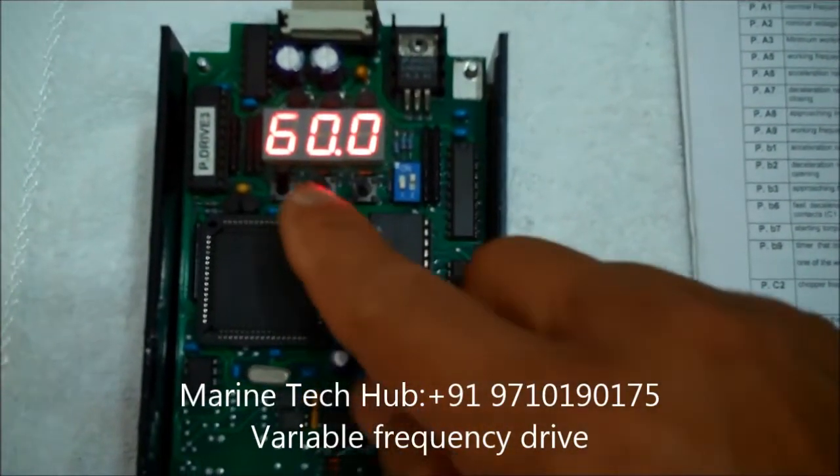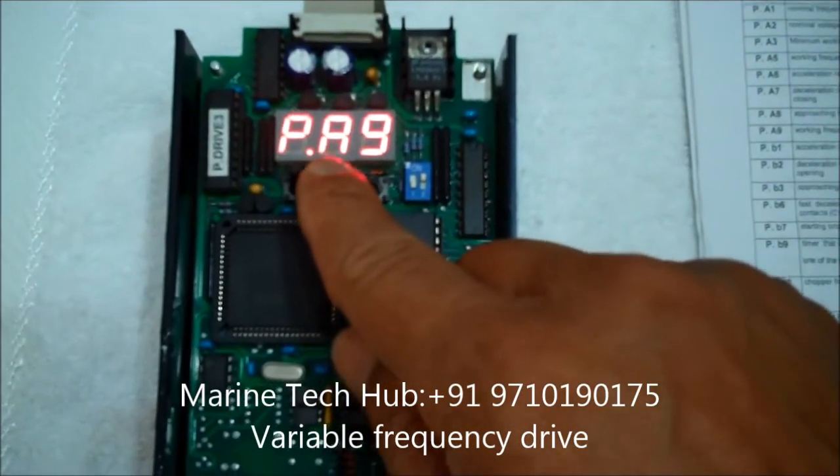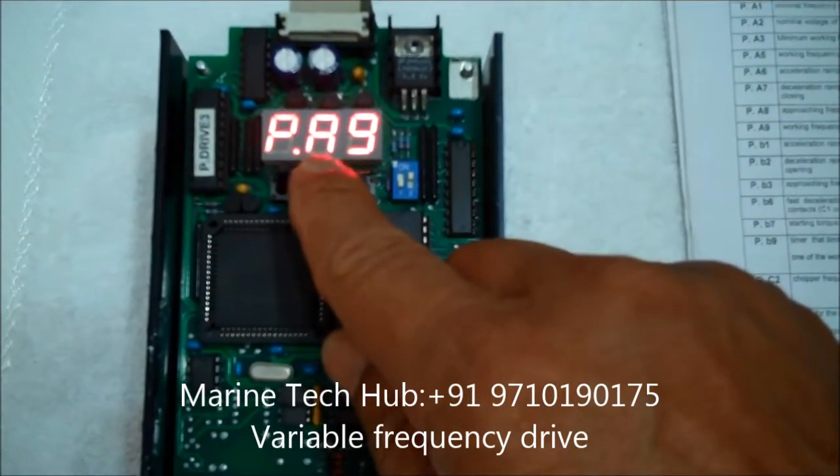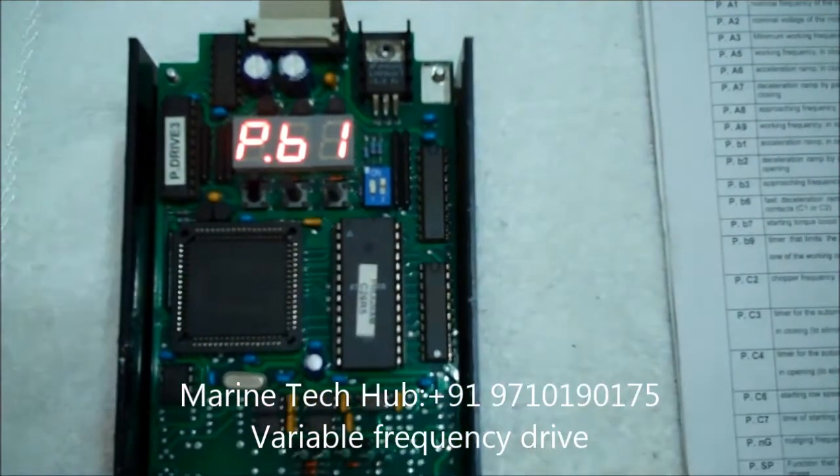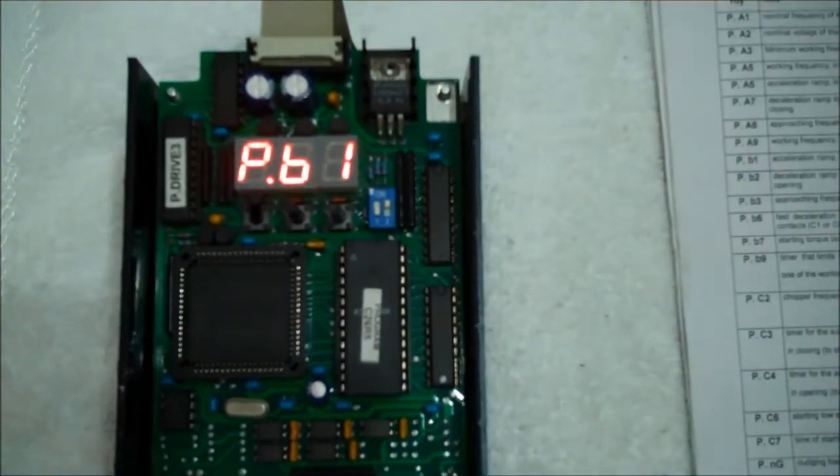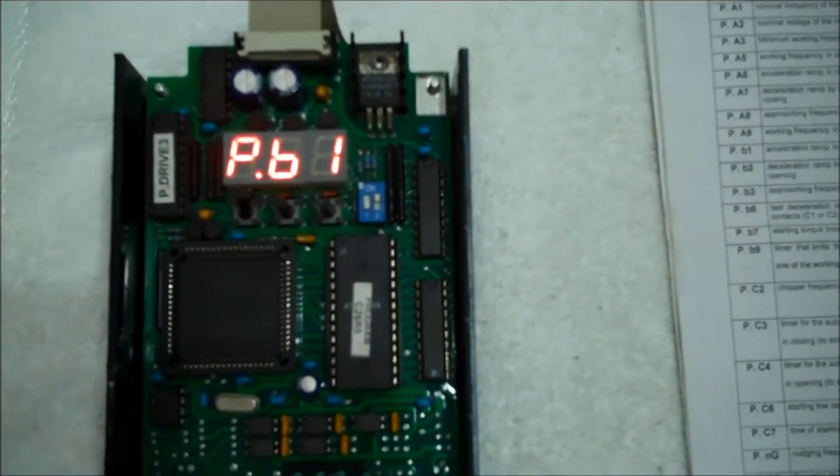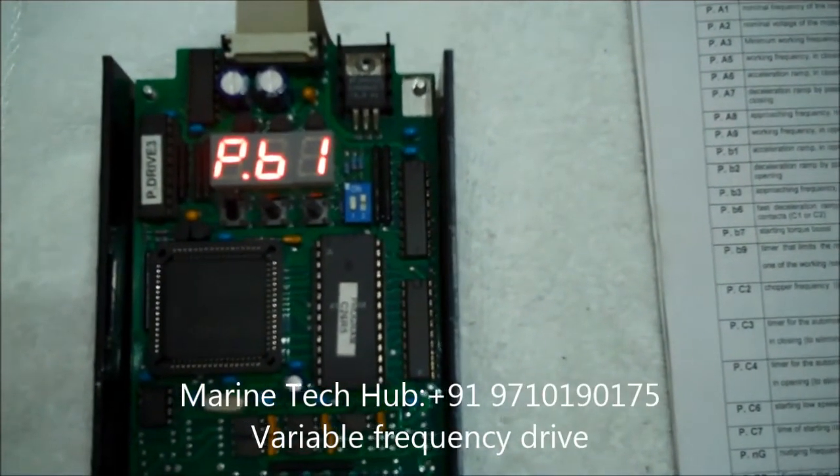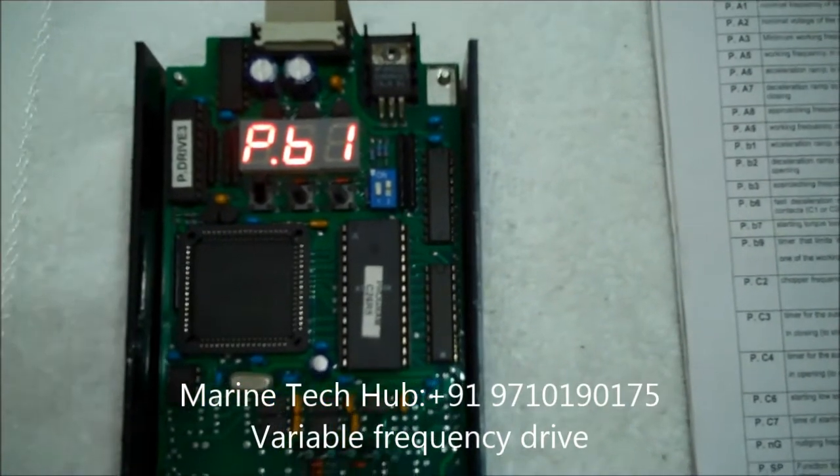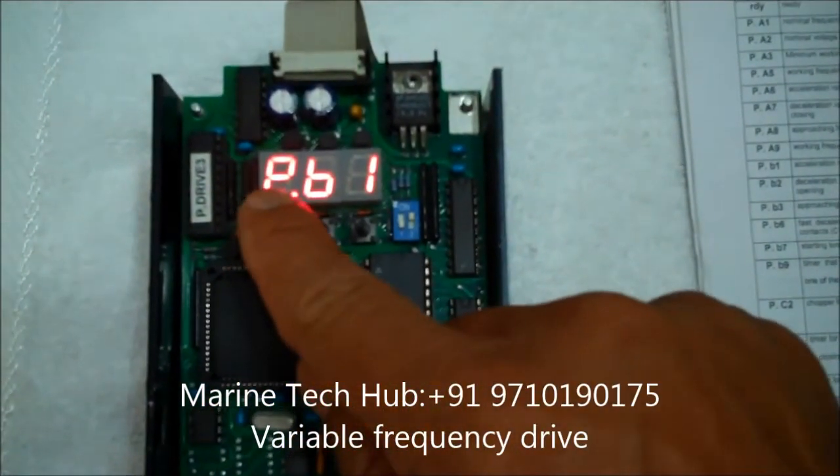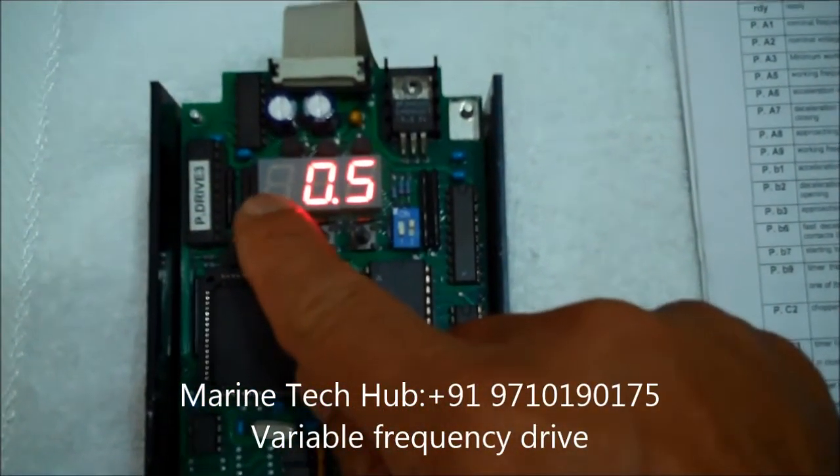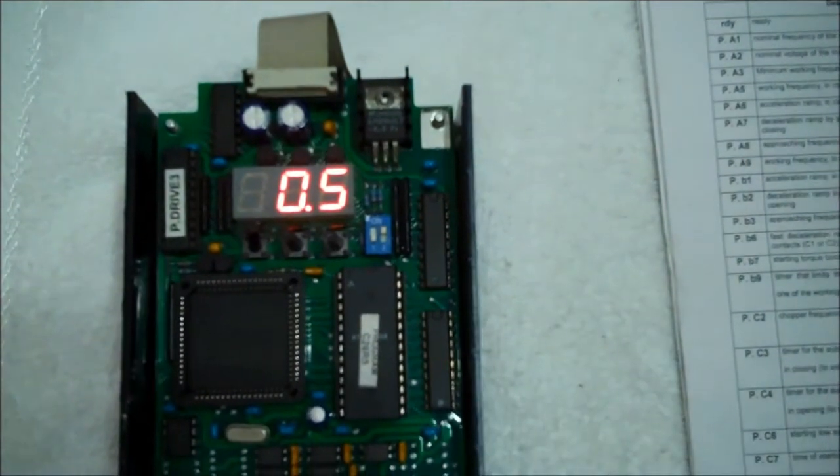So next I will go to the next screen. This is PB1. PB1 is acceleration ramp in opening. This is in seconds. So this is programmed for 0.5 seconds. You can see that.